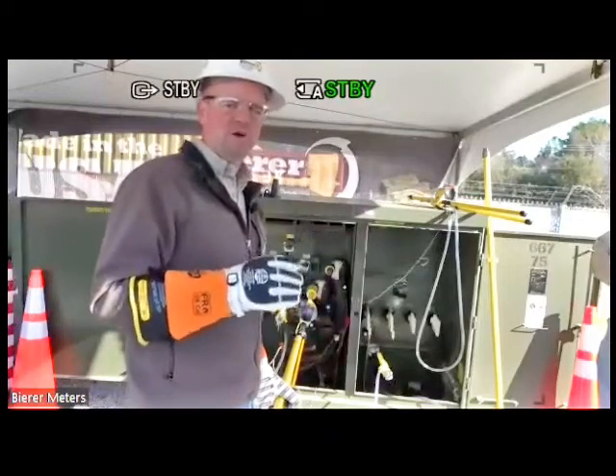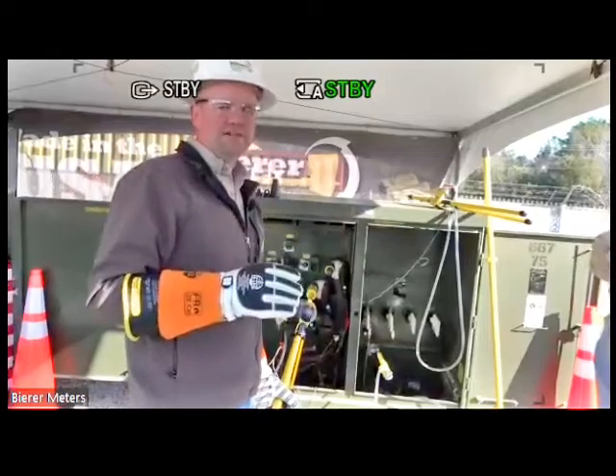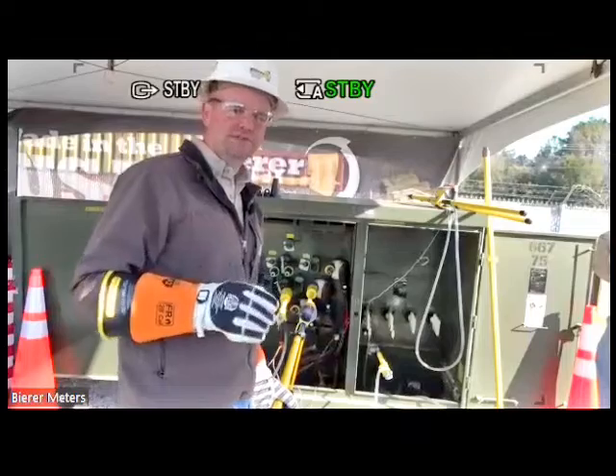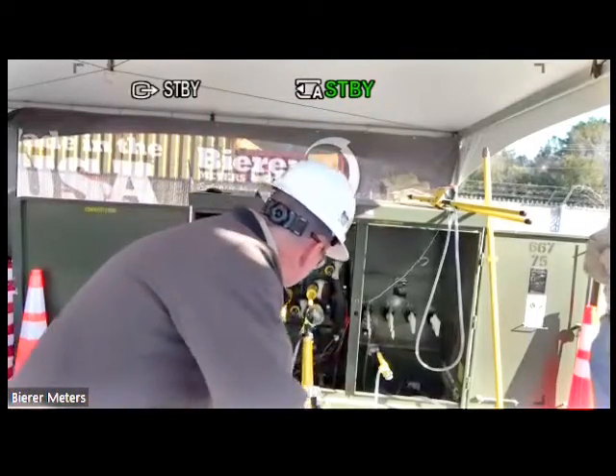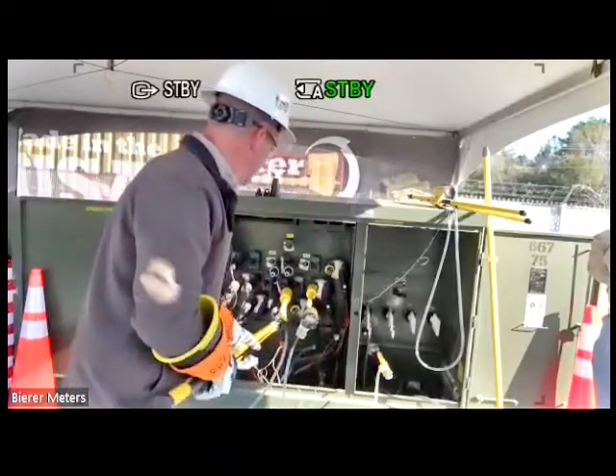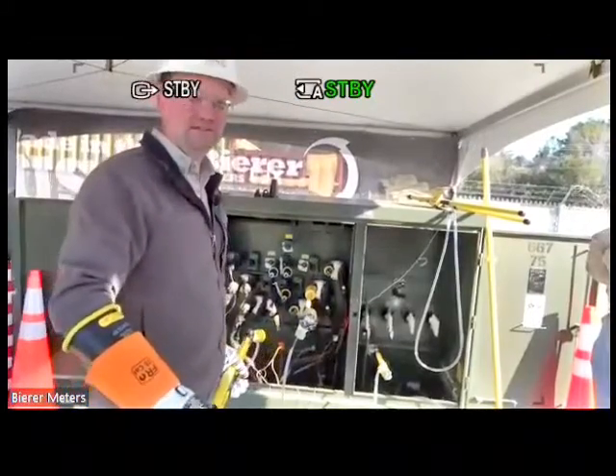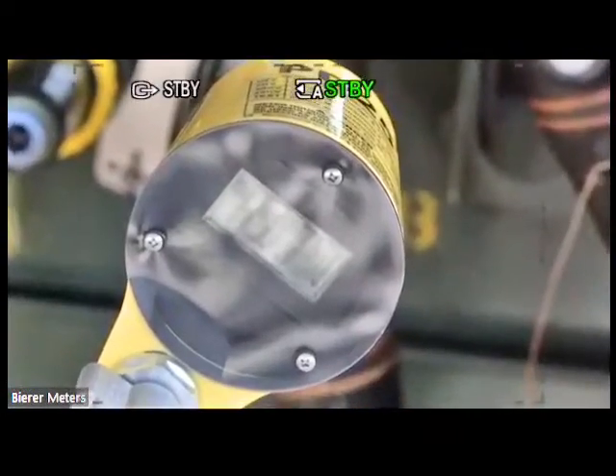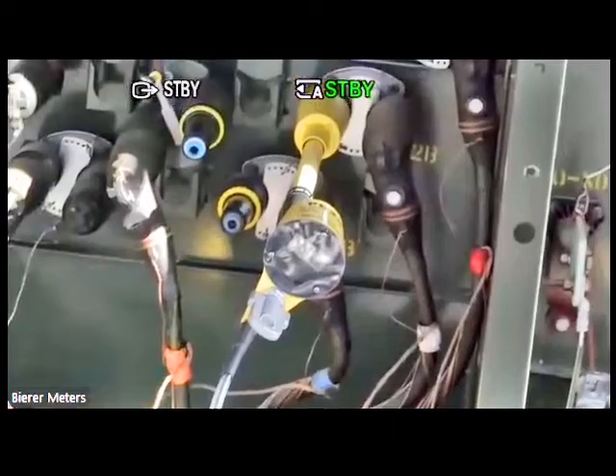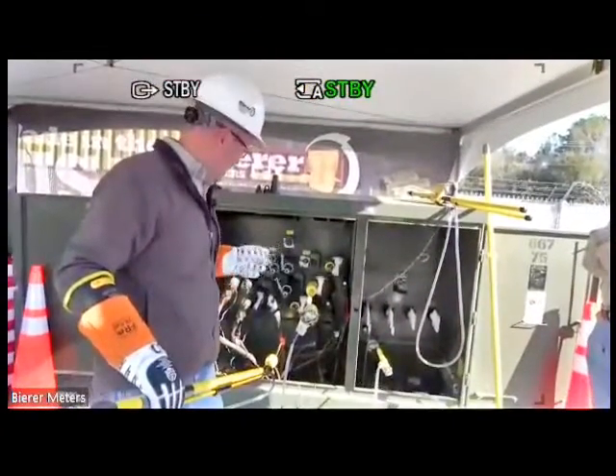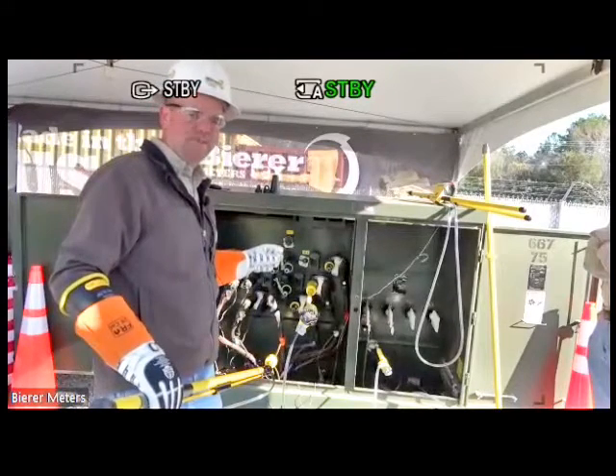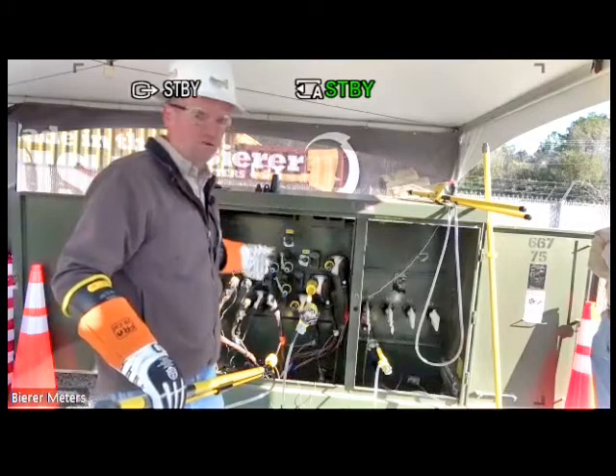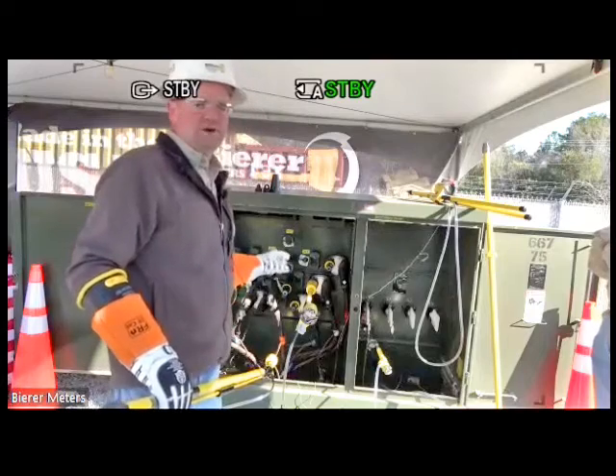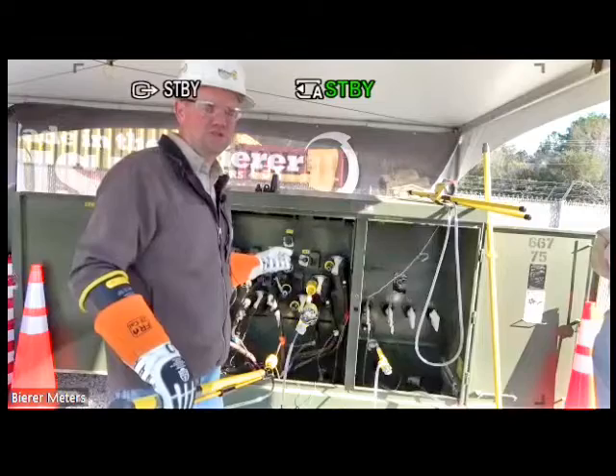Now, if this cable has a bolted fault, in other words, it's truly grounded, this number will be roughly 70% of phase to ground. Now, what does that mean? That means that it would be no different from essentially testing the high pot. So if I leave this high pot attached to an energized phase like this, and I take this second probe and touch the ground, you see that it's roughly about 10 kV thereabouts, right? And this is close to 14, it's 13.8 phase to ground. So there's your roughly 70% phase to ground. But remember what I mentioned earlier. I'm actually testing the high pot doing this, so I can verify that the high pot is a good accessory, a good adapter before I go using it. Okay. But that's what you would see on a bolted fault, is that number right there.